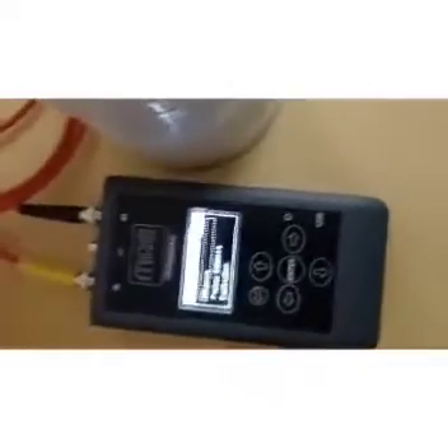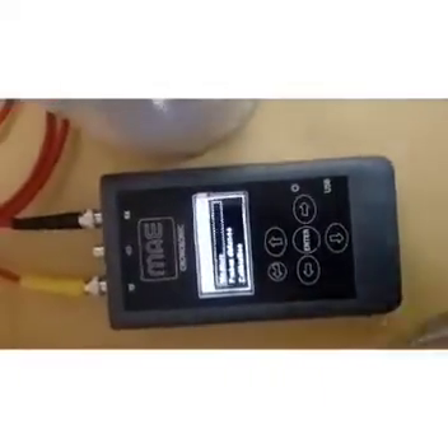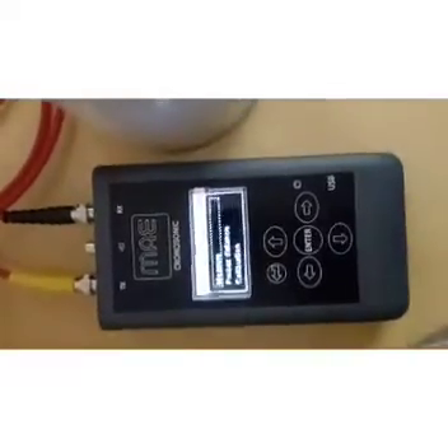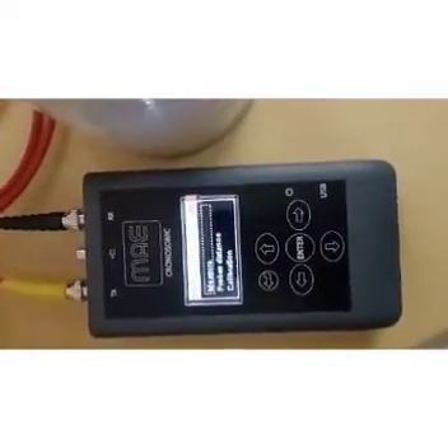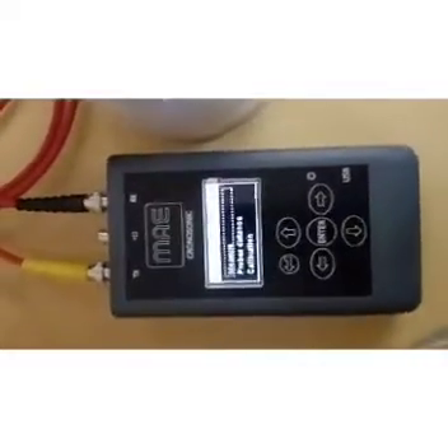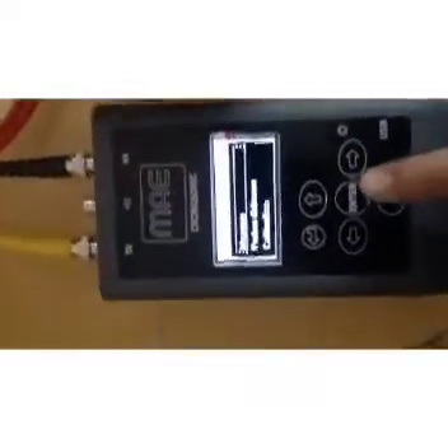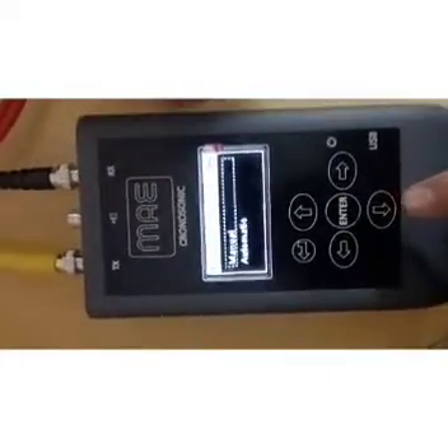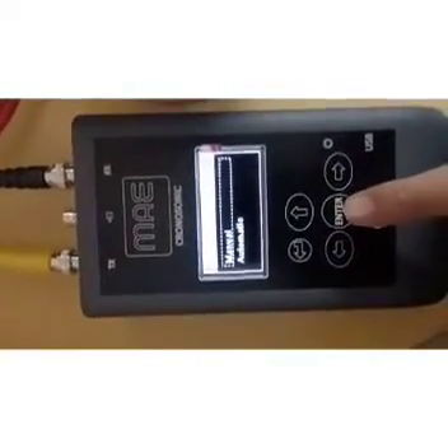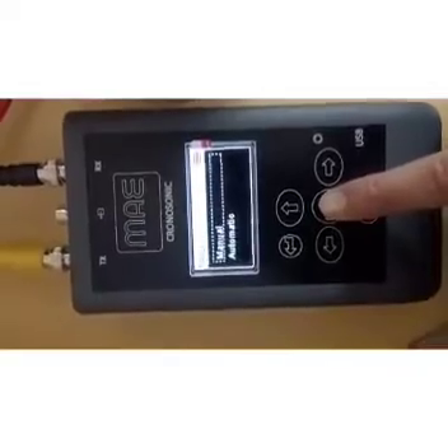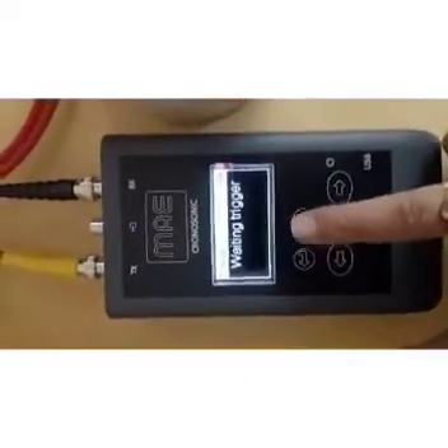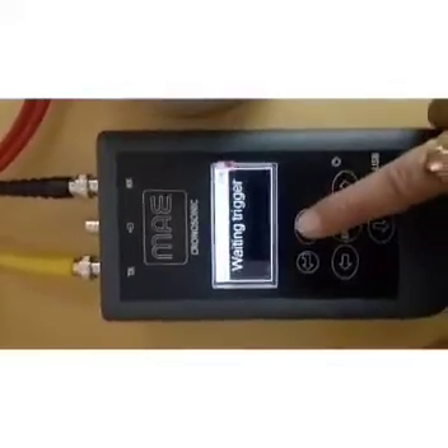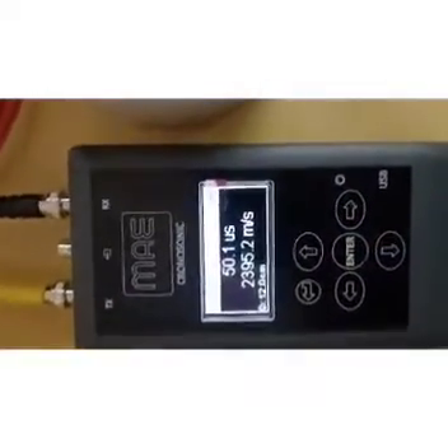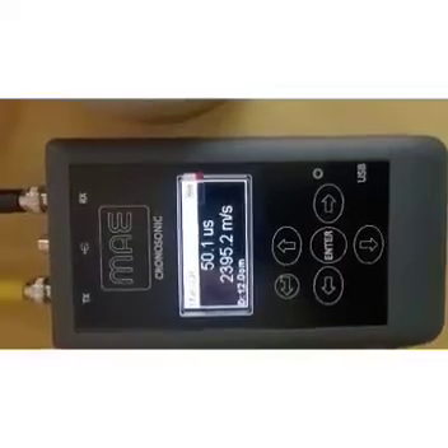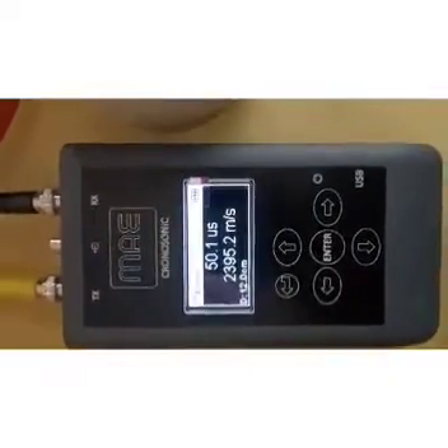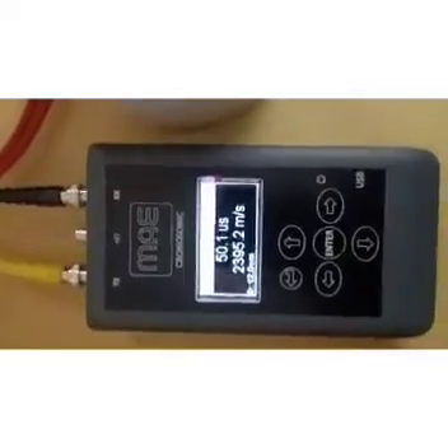By doing so, we are also checking the transit time of the calibration bar, so as to ensure that the values are coming exactly as written over there. Manual and automatic, these are two modes. We are going to use the manual mode. When this comes, waiting trigger, you have to press the upper button like this. So 50.1 microseconds. This is the value which comes out, which matches the value written over there.